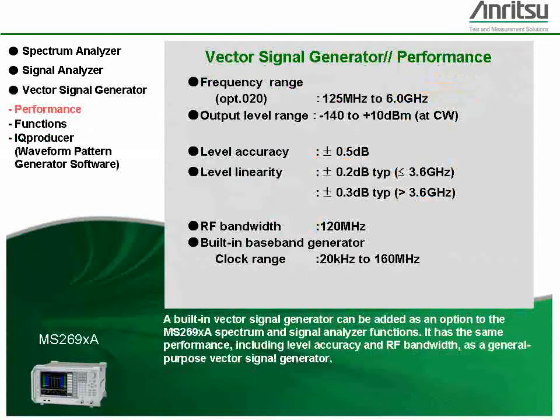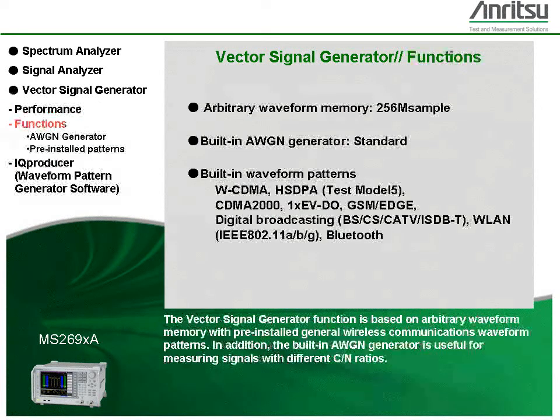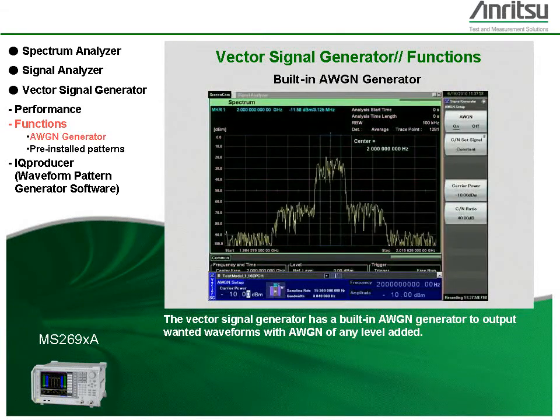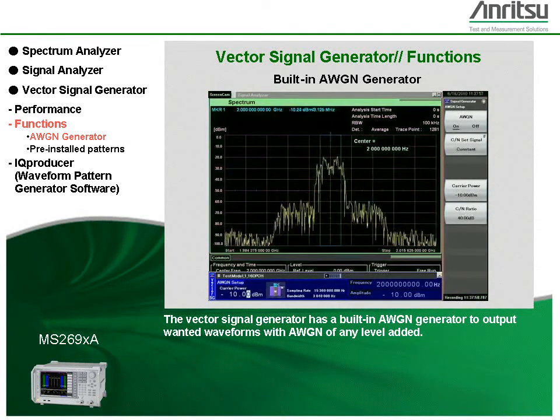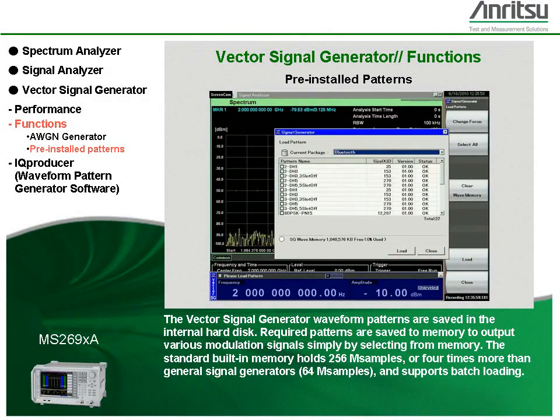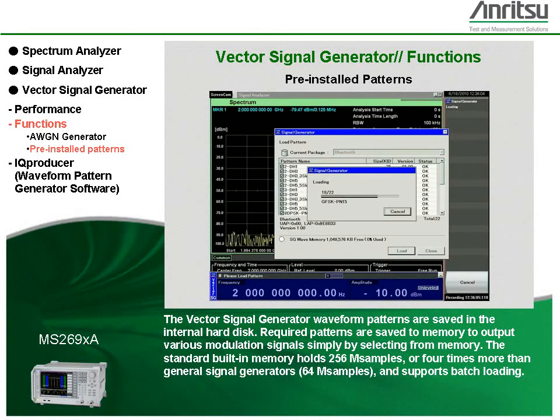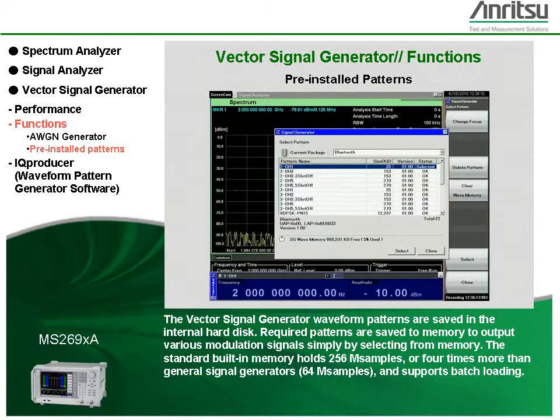A built-in vector signal generator can be added as an option to the MS269XA spectrum and signal analyzer functions. It has the same performance, including level accuracy and RF bandwidth, as a general-purpose vector signal generator. The vector signal generator function is based on arbitrary waveform memory with pre-installed general wireless communications waveform patterns. The built-in AWGN generator is useful for measuring signals with different carrier-to-noise ratios, allowing wanted waveforms to be output with AWGN of any level added. Waveform patterns are saved in the internal hard disk, and required patterns are saved to memory to output various modulation signals simply by selecting from memory.